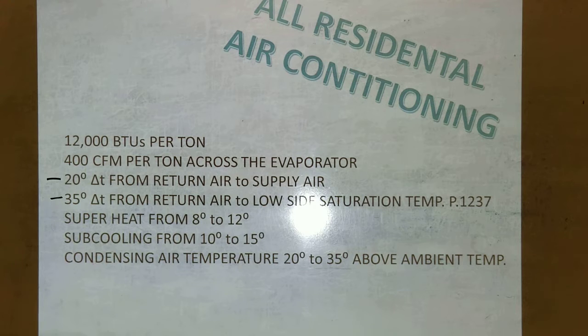Many technicians use the terms approach temperature or temperature split to describe the difference in temperature between heat exchange mediums. For example, the difference in temperature between the indoor coil and the return air for a central air conditioning system, 35 degrees Fahrenheit for standard air conditioning equipment. The condenser also has an approach or split temperature. These temperatures are used by the technicians to determine when a heat exchanger is functioning correctly. For example, when an air cooled condenser approach temperature begins to increase, it is a sign that the condenser is not condensing efficiently. This tells the technician that the coil is dirty or that there is not enough air passing through the coil.